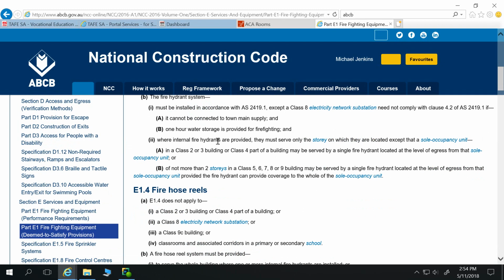Where internal fire hydrants are provided, they must serve only the story on which they are located, except that a sole occupancy unit, class 2 or 3, we're not that, or of not more than 2 stories in a class 5, 6, 7, 8, 9 building, may be served by a single fire hydrant located at the level of egress from that sole occupancy unit, provided the fire hydrant can provide coverage to the whole of the sole occupancy unit.